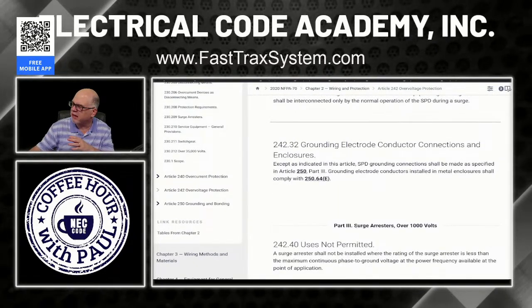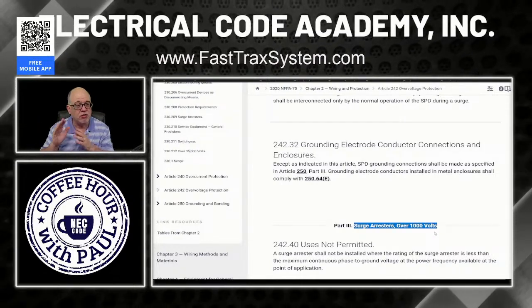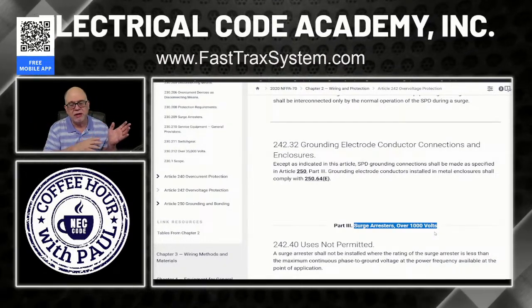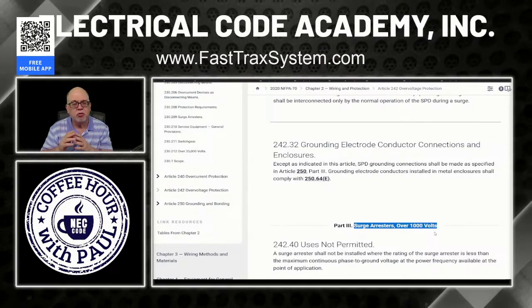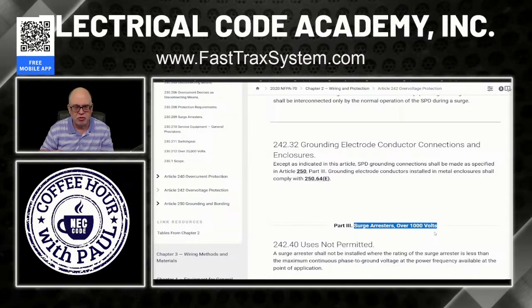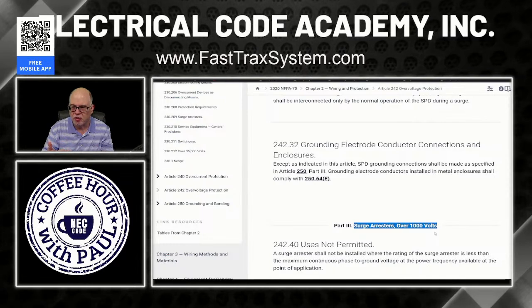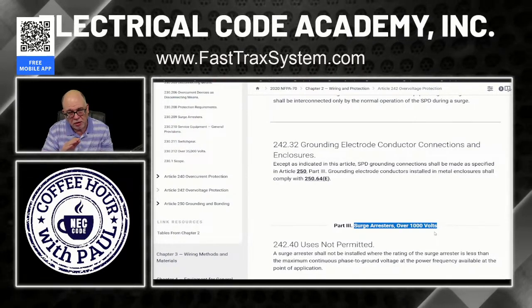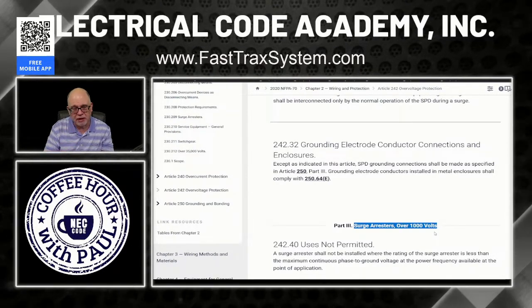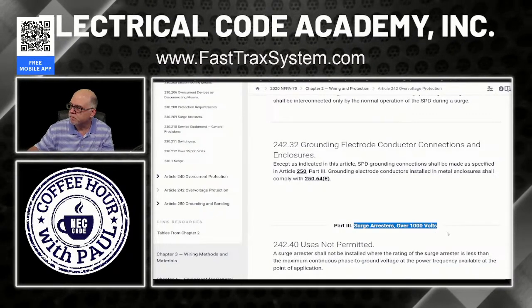And of course, you also have surge arresters, which are over 1,000 volts. That's also here as well. That was also in a different article, and it was relocated here to 242, right? So it's all conveniently located in Article 242 if you want to learn the different types of SPDs and their applications and all that. But when it comes to services, the direct requirement to install SPDs comes from 230.67, okay?